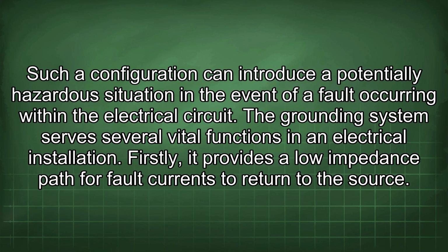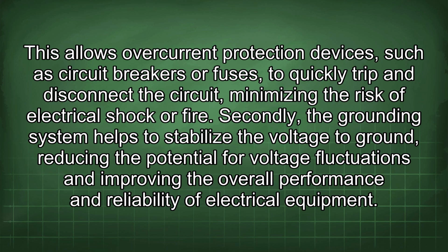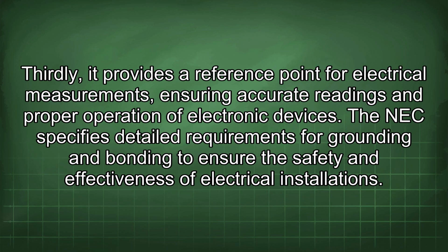The grounding system serves several vital functions in an electrical installation. Firstly, it provides a low impedance path for fault currents to return to the source. This allows overcurrent protection devices such as circuit breakers or fuses to quickly trip and disconnect the circuit, minimizing the risk of electrical shock or fire. Secondly, the grounding system helps to stabilize the voltage to ground, reducing the potential for voltage fluctuations and improving the overall performance and reliability of electrical equipment. Thirdly, it provides a reference point for electrical measurements, ensuring accurate readings and proper operation of electronic devices.